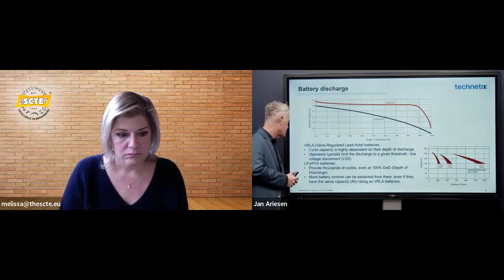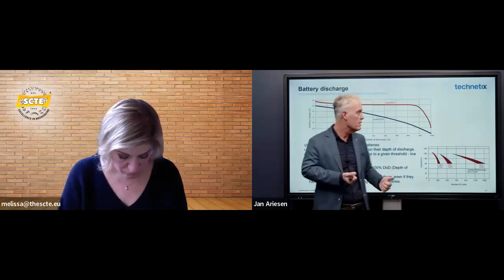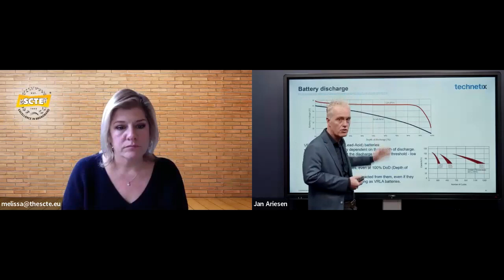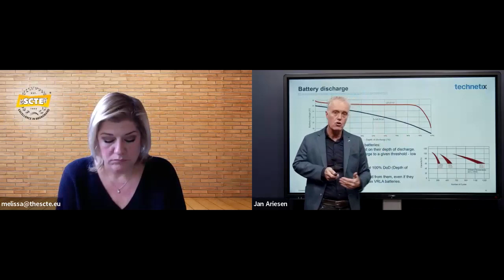I know this is a side step, but it's important to see, especially with lead acid batteries, that discharging is very critical. In my previous slide I showed that because the current is lower, the efficiency of DC-DC versus DC-AC conversion is better, therefore the uptime of the battery is longer, therefore you don't have to discharge your batteries as far, therefore the lifetime of your battery benefits. So it all works in your favor by reducing the current in the network.